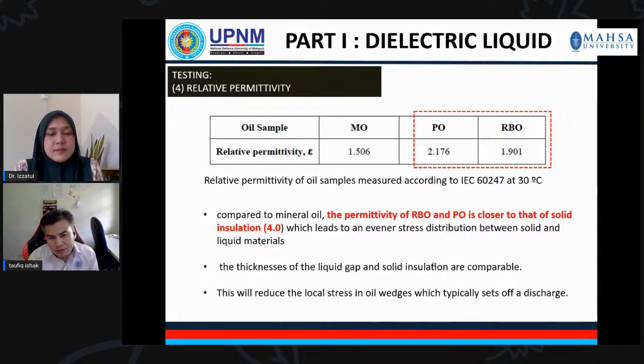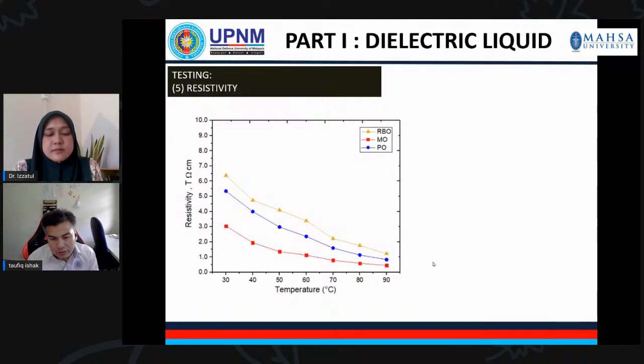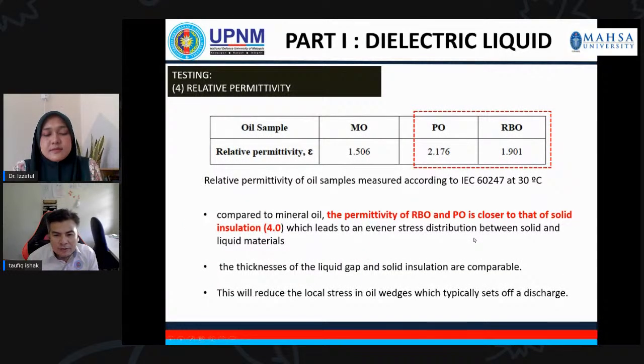So when we compare mineral oil and vegetable oil, the good thing about vegetable oil is that its relative permittivity is close to that of the paper or solid insulation inside the transformer, which is roughly around 4.0. When you have a value nearer to the solid insulation, you will have an even stress distribution between the solid and liquid material as compared to mineral oil. This means the electrical stress experienced by the solid insulation and liquid insulation will be evenly distributed when you use palm vegetable oil as compared to mineral oil. In mineral oil, you will have higher stress as compared to vegetable oil.